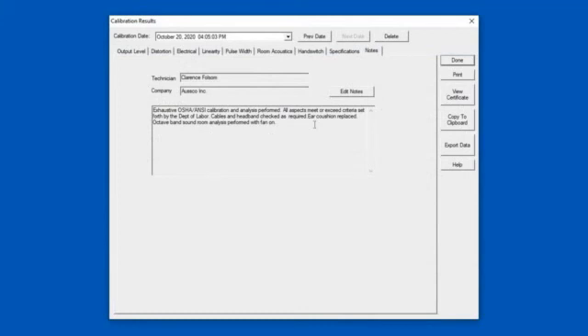Done. Save the results. If I want to take a look, I can come back up here or print it. Here's an area for putting in notes — I can edit them, add new ones, whatever I want. Or if I want to look at something in the output level, there it is. Let's view the certificate. I can select what I want to print, including the pre-recording. And there's the calibration sheet — those spots that were out of calibration are documented. The calibration sheet has everything on it, every possible function that that audiometer can do. Thanks for watching — if you have some questions, give me a call.